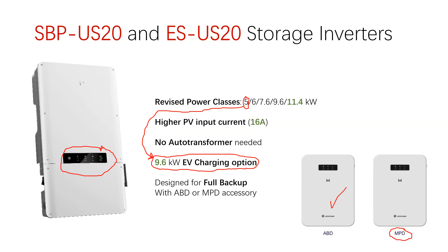That is a special option, so you'd have to ask for that in particular. But it bypasses the normal circuitry inside the inverter, which is why you can do 9.6 of charging power out of a 5 kilowatt inverter. Just remember when you're doing your breaker sizing with this option, that you're doing 9.6 of AC pull and not just something less. You're not just pushing 5, but you're pulling 9.6.